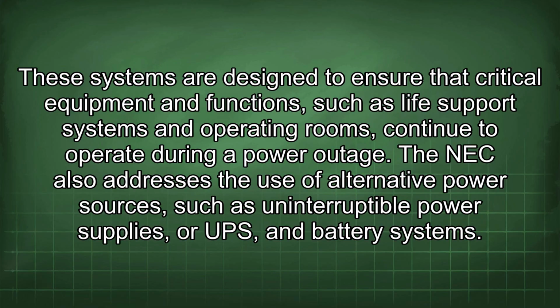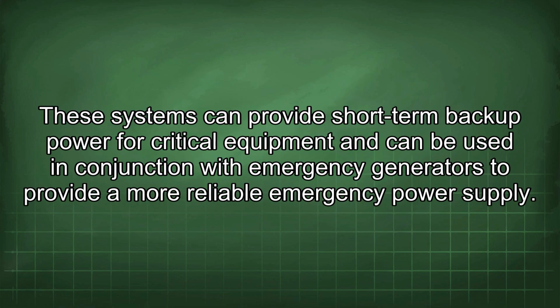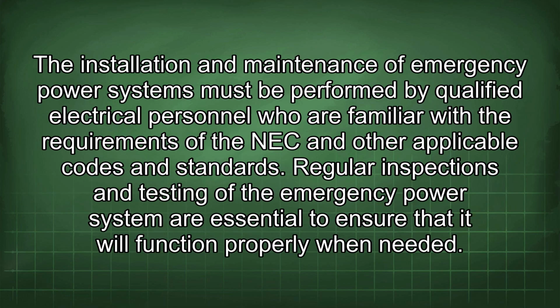The NEC also addresses the use of alternative power sources, such as uninterruptible power supplies, or UPS, and battery systems. These systems can provide short-term backup power for critical equipment and can be used in conjunction with emergency generators to provide a more reliable emergency power supply. The installation and maintenance of emergency power systems must be performed by qualified electrical personnel who are familiar with the requirements of the NEC and other applicable codes and standards.